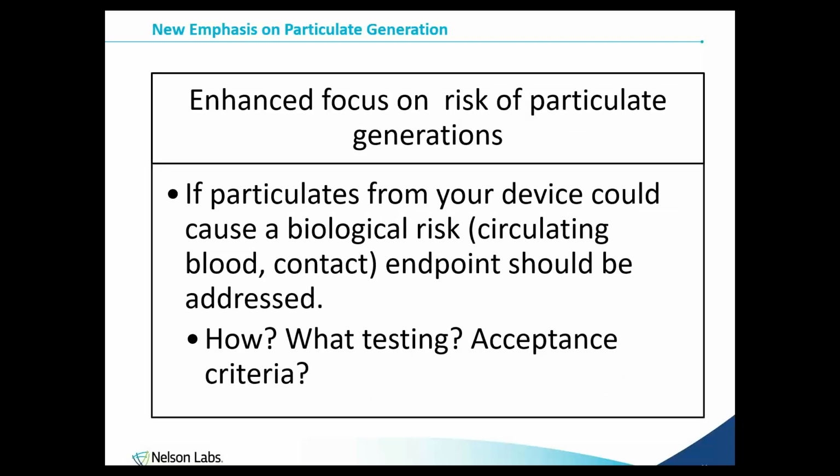So one of the other things that this standard is bringing in, specifically for devices where this is a potential risk, and vascular devices definitely fall in there, is particulates from your device. And so when you start looking at different types of biological exposures where particulates could be a concern, orthopedics could be a concern for particulates for sure, especially in joint spaces. But one of the bigger ones are neuro and vascular. And so we're starting to see this a lot from the FDA already.